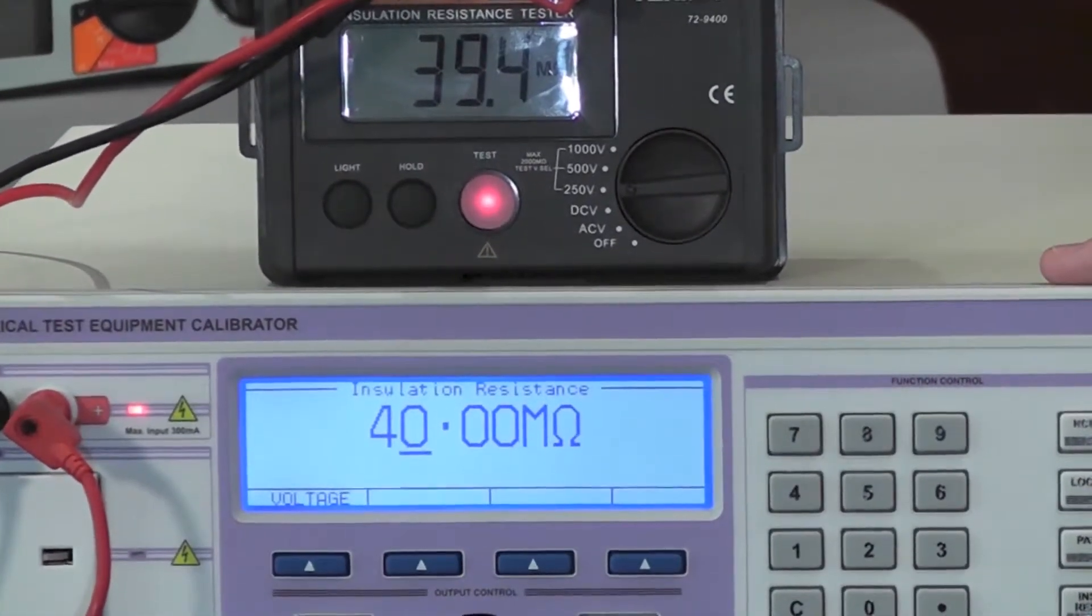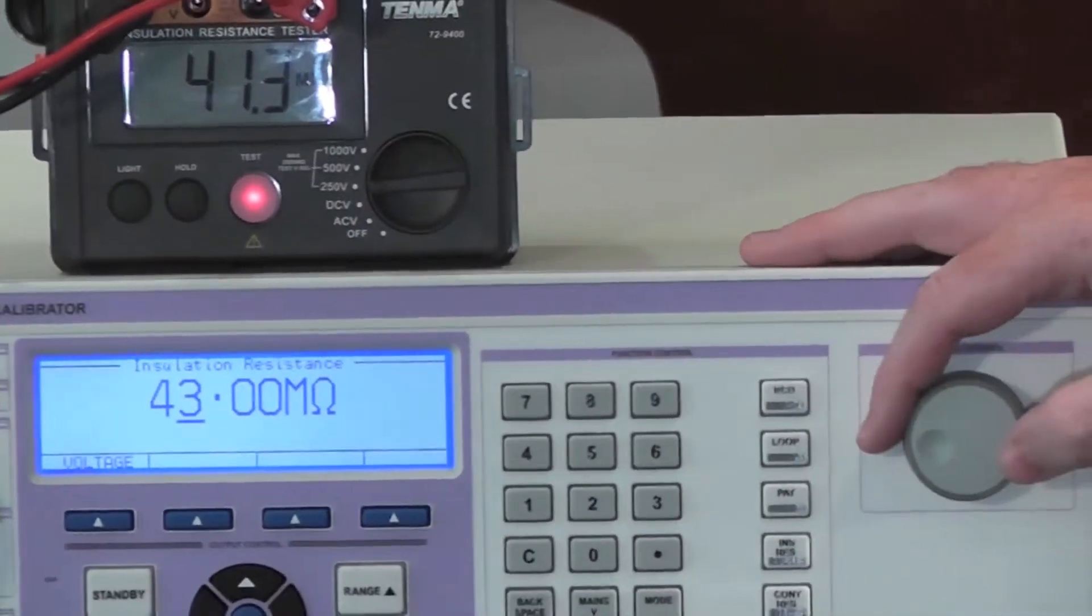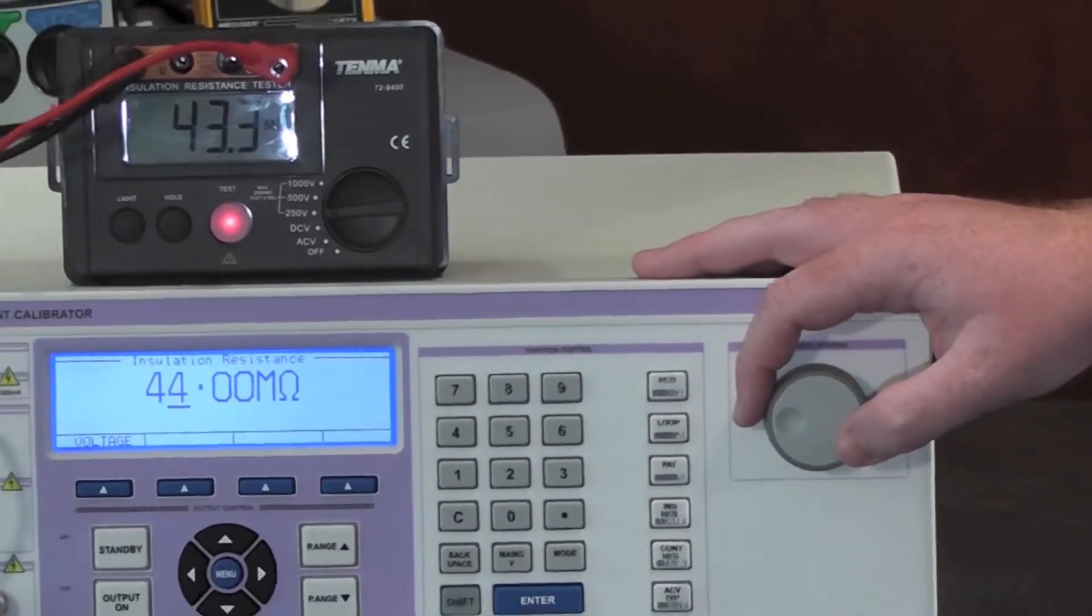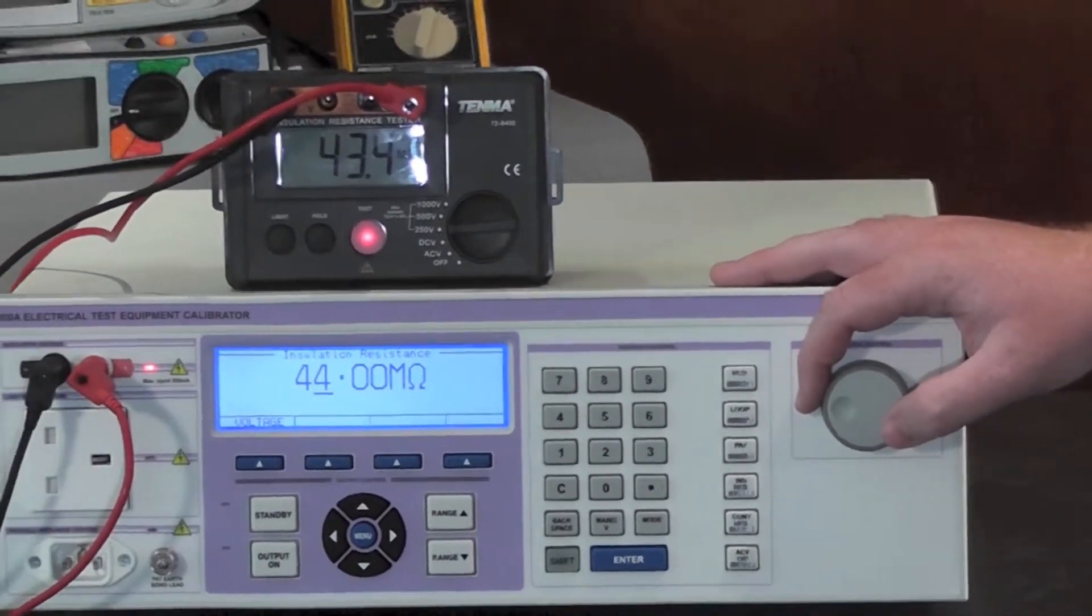The output resistance can be varied using the digital control. The 3200A is fitted with insulation resistance to 2 gigaohms as standard but can be extended to 10 gigaohms.